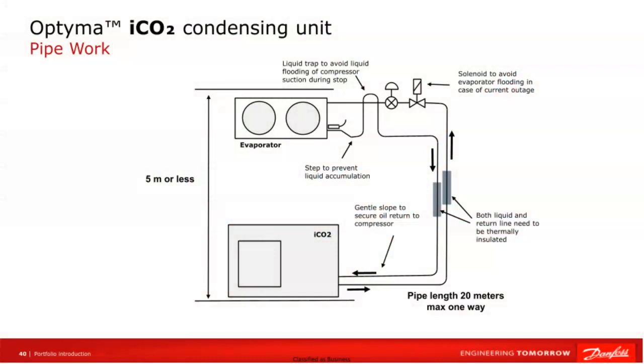Now, we will deal with issues related to running the installation. We will discuss what elevation we can take into account and what maximum pipeline lengths can be used in our refrigeration system. What should you pay attention to if we have an installation where the evaporator is mounted at the top and the condensing unit at the bottom? There are some key points worth considering.